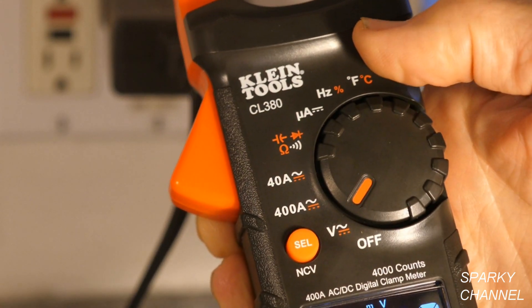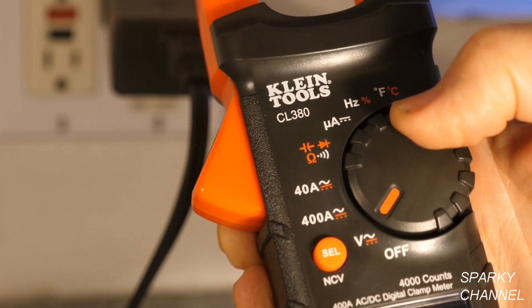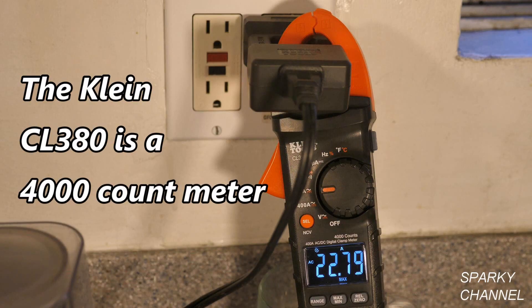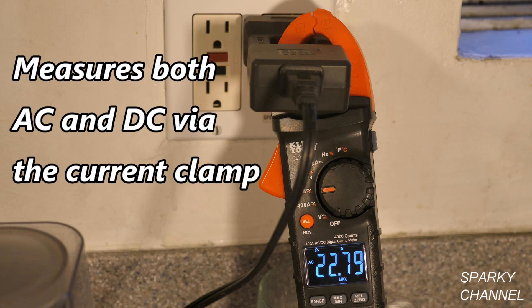You have 400 amps for higher amperage, but if you're measuring less than 40 amps, put it on 40 amps for better resolution. This is a 4000-count meter, which means if you measure just under 40 volts AC it will read 39.99 — two digits past the decimal point. But if you measure 40 volts AC it reads 40.0. That's what 4000 count means, and it's pretty good for this price range.